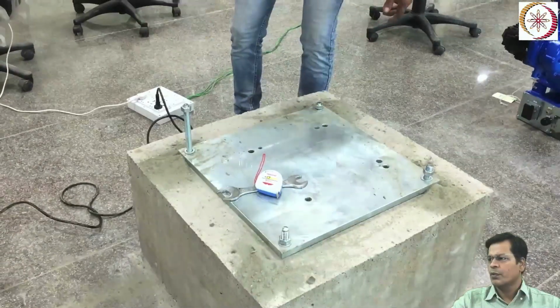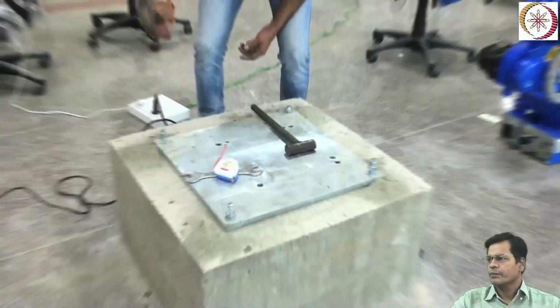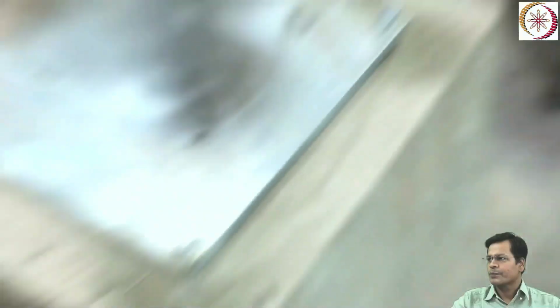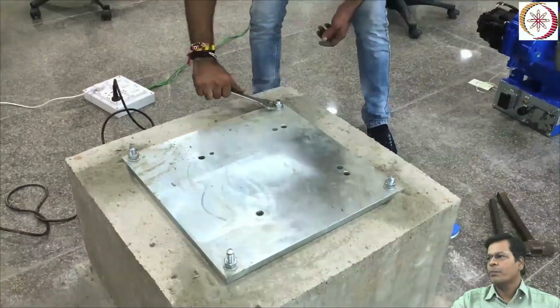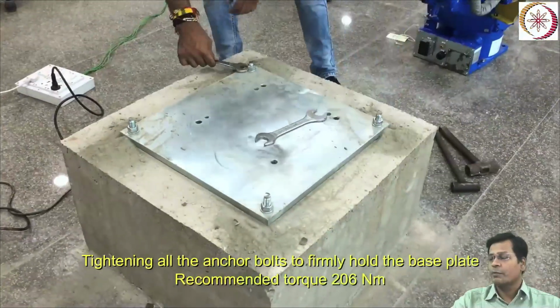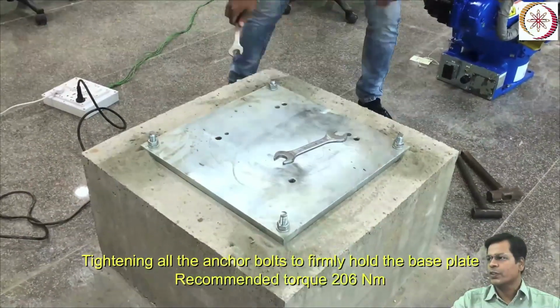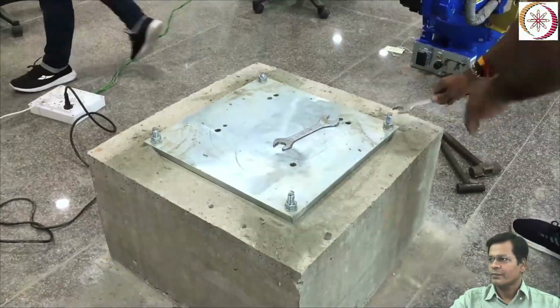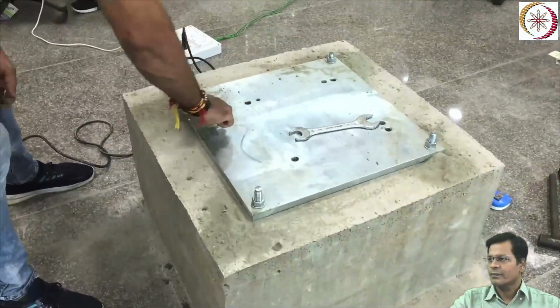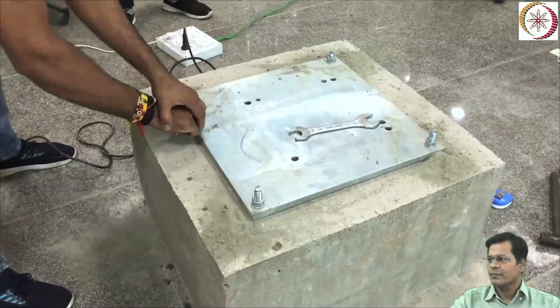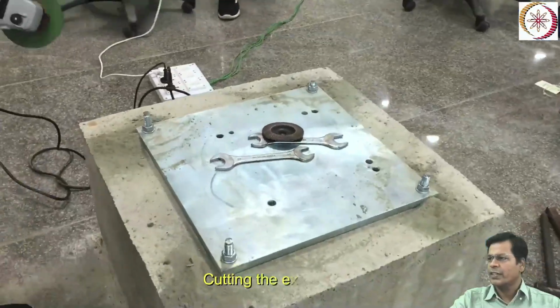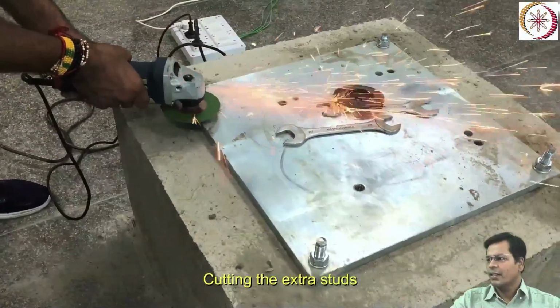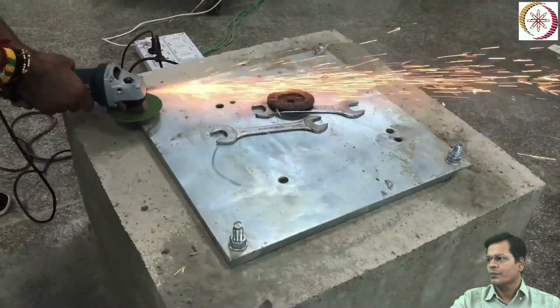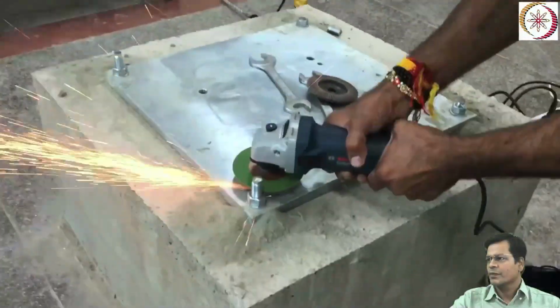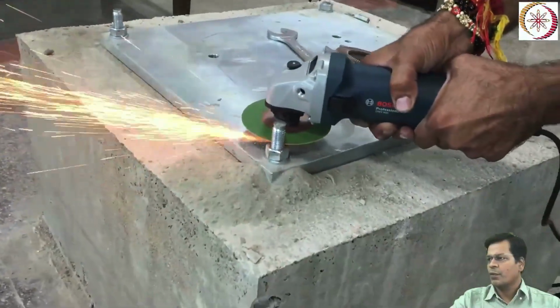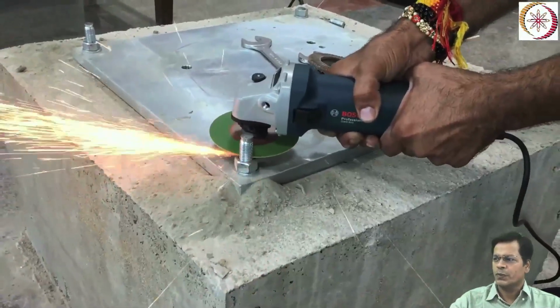All the bolts are now put in. I am quickly forwarding it now. All the bolts are fully tightened to the recommended torque, as discussed earlier, 206 Newton meter. Once fully tightened, you can cut the extra part which remains. All the bolts are cut and properly ground before it is put to use.